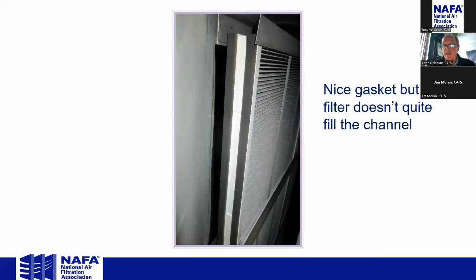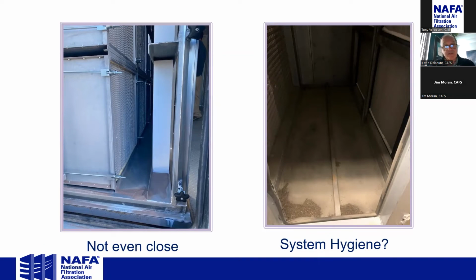In this case, you see a very high efficient pleated mini pleat type filter, but again, it doesn't come to the end of the tracking, and the gaskets don't seal the filter to the door, allowing for potential and probable ample bypass around that filter. On the left-hand side, these are HEPA filters being protected by a filter that doesn't come to the door. So a substantial amount of the air is going to bypass that pre-filter and go directly in the HEPA filter, increasing the pressure drop, reducing the effective service life of that filter, and increasing the overall cost of the system.